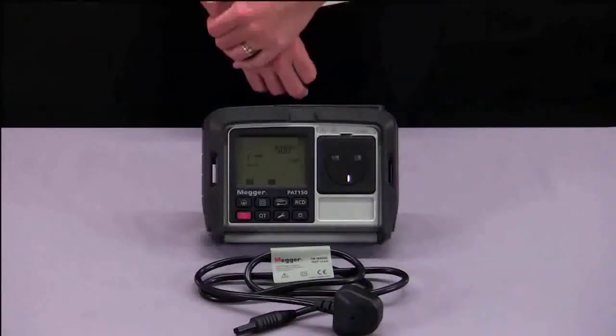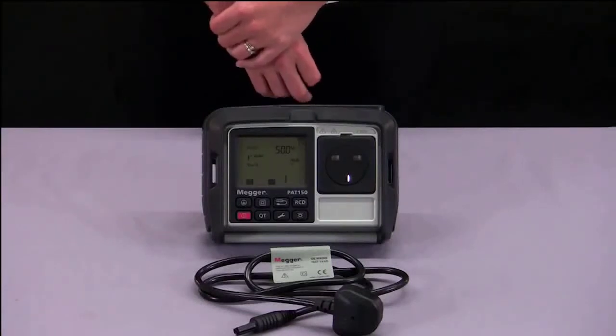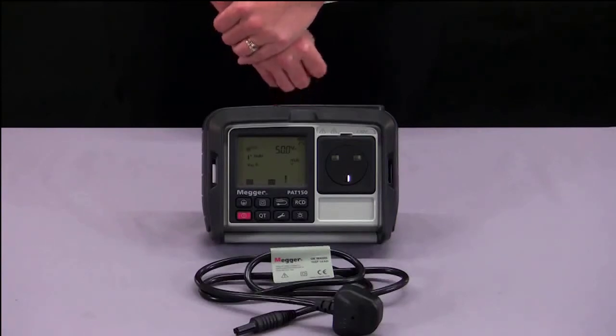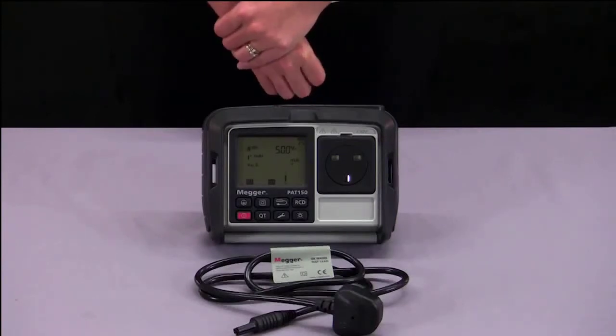The PAT150 and the 150R can be plugged into a main supply to enable live leakage testing, such as your differential leakage test and your touch current leakage test. You can also check the functionality of your appliance, as well as testing portable RCDs.